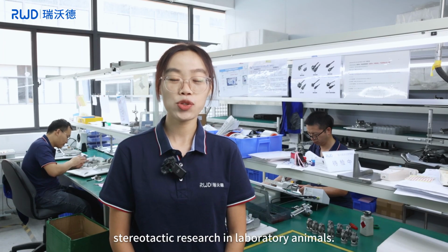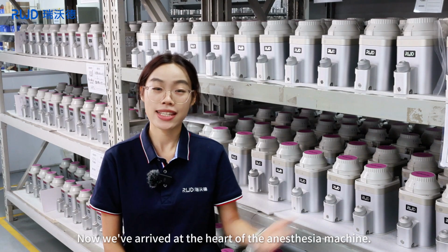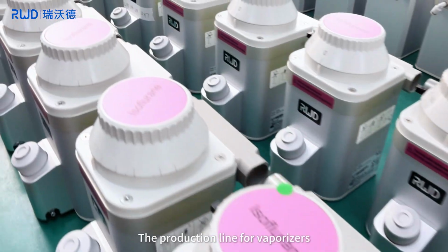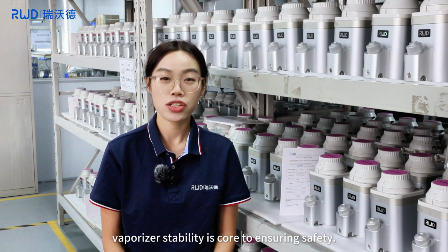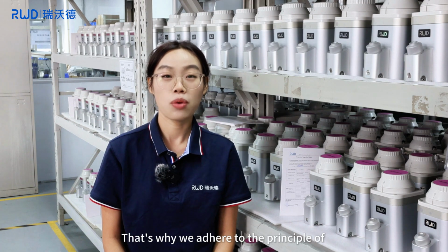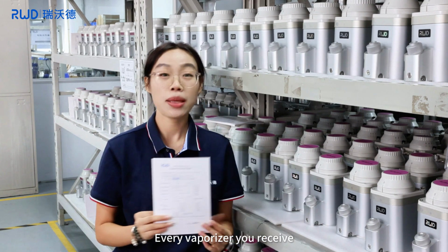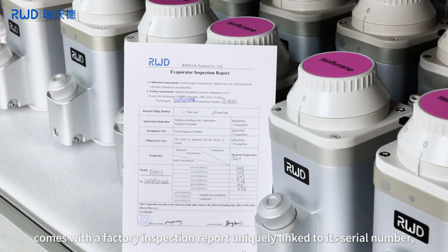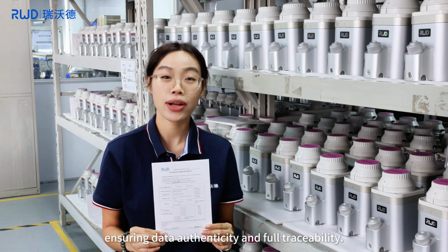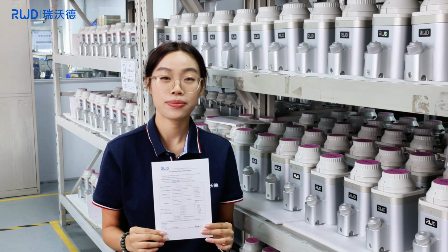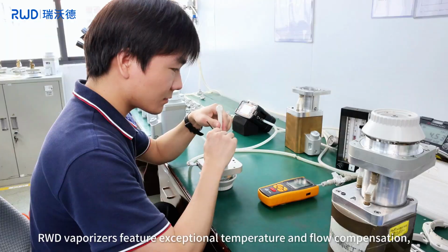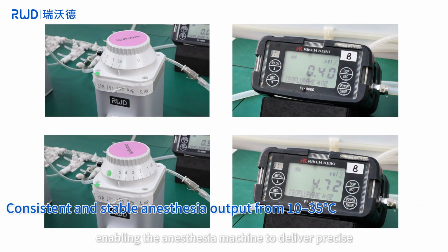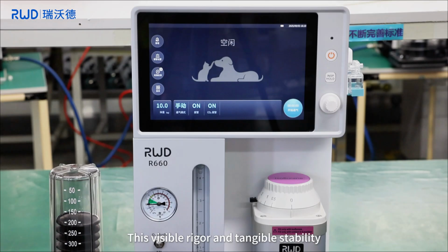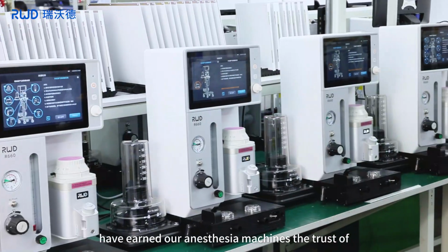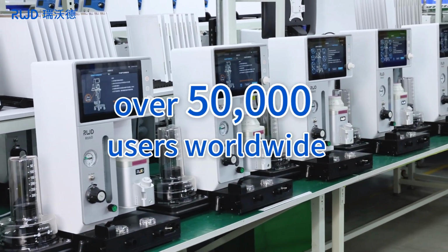Now we've arrived at the heart of the anesthesia machine, the production line for vaporizers. For anesthesia machines, vaporizer stability is core to ensuring safety. That's why we adhere to the principle of one machine, one report. Every vaporizer you receive comes with a factory inspection report uniquely linked to its serial number, ensuring data authenticity and full traceability. RWD vaporizers feature exceptional temperature and flow compensation, enabling the anesthesia machine to deliver precise and stable anesthesia output in a wide temperature range. This visible rigor and tangible stability have earned our anesthesia machines the trust of over 50,000 users worldwide.